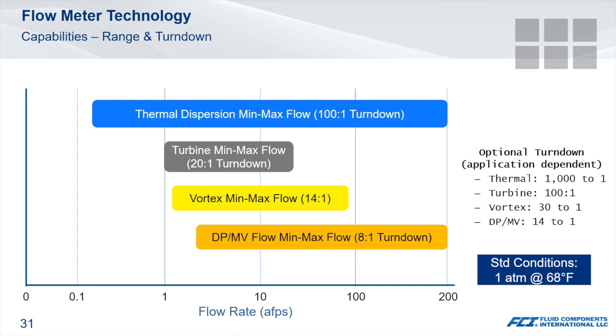Flow range turndown is also a factor that could impact our measurement. Many applications have varying demands. For example, you may see a very low flow pilot condition to keep a piece of equipment in standby mode that suddenly requires ramping up to 50% capacity or more. Properly sizing and selecting for these conditions requires clearly defined minimum and maximum flow values.